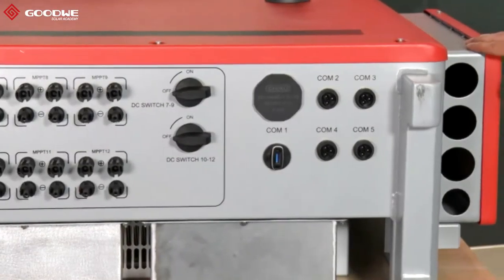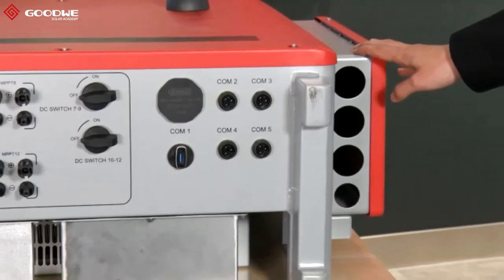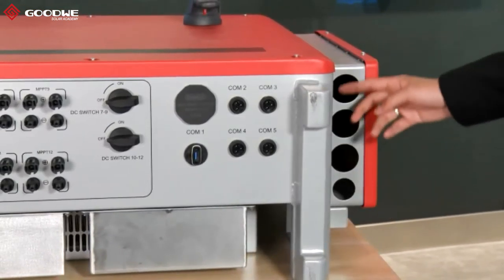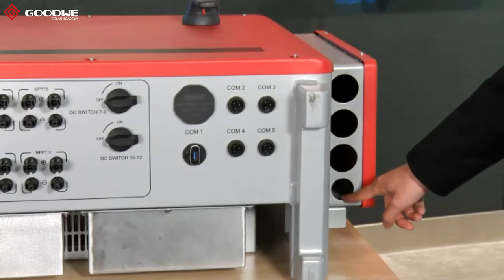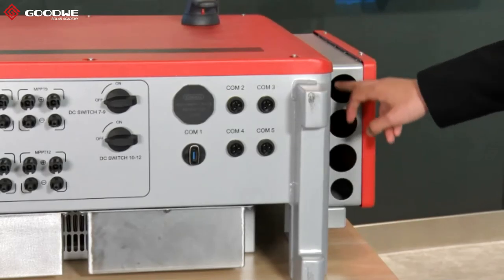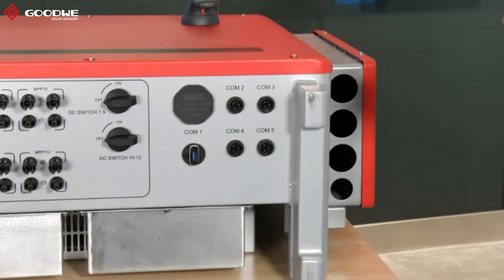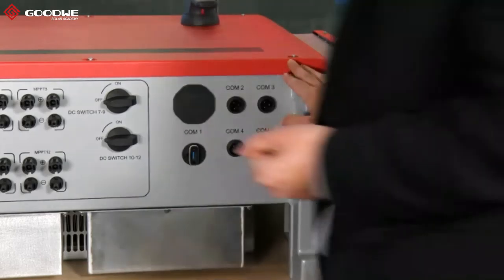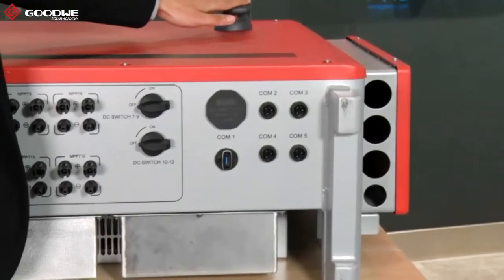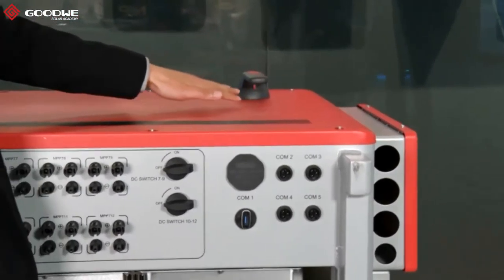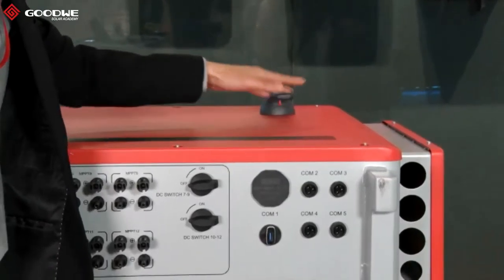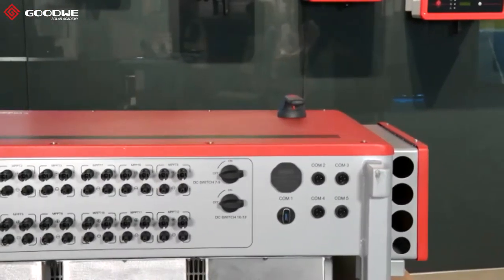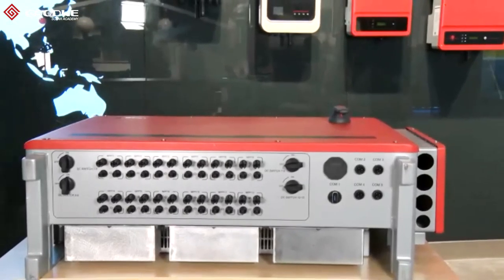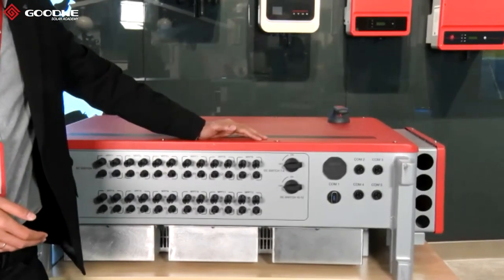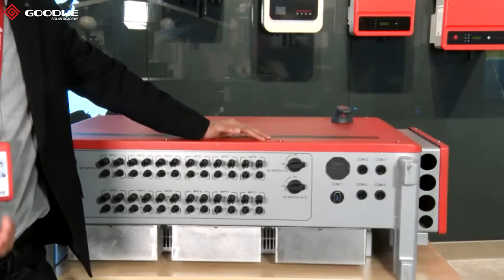And here is our AC cable box. You can find L1, L2, L3, and here the neutral line. For each of L1, L2, L3, the maximum we can support is 250 square millimeters. And here you can find an AC breaker. The AC breaker is optional, which means you can choose an inverter with or without the AC breaker. So that's our HT series. It will be released very soon, in May and also in July.